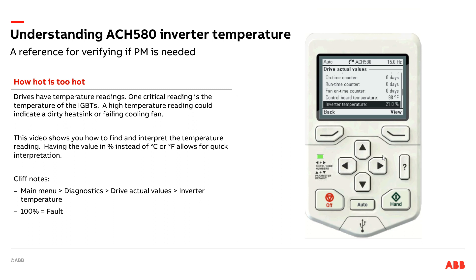So don't wait for the drive to go into a warning or fault state, because drives are like any other electronic device. You keep it cool, you keep it clean, you keep it dry — it's going to last longer, just like my TV, just like my laptop. If those devices run cooler, the electronics are going to last longer. Drives are the same way. So don't rely on the drive warning or the drive fault to kick in to let you know there's a problem. It's something great for you to trend through your building automation system.